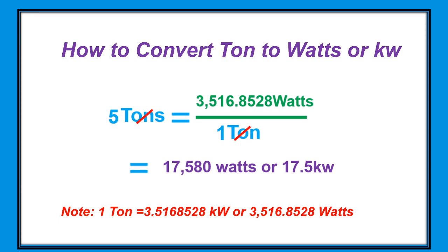Next, how to convert tons to watts. Note: one ton equals 3.516 kilowatts, or 3,516 watts. For example, 5 tons times 3,516 watts per ton — canceling the tons — gives us 17,580 watts, or 17.5 kilowatts.